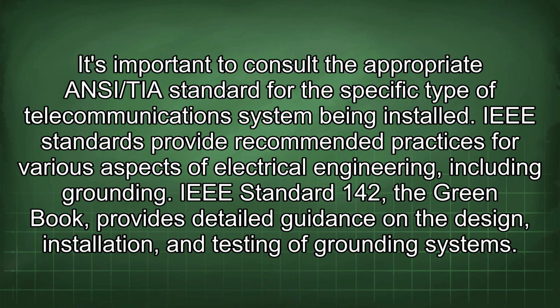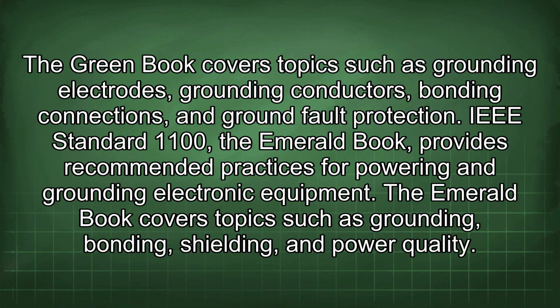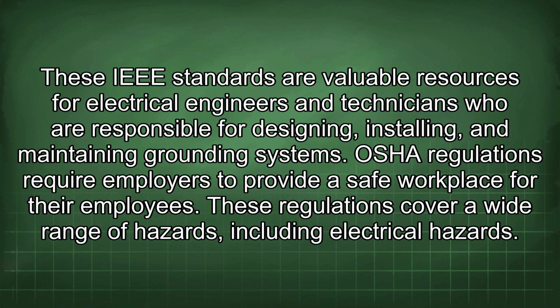IEEE standards provide recommended practices for various aspects of electrical engineering, including grounding. IEEE Standard 142, the Green Book, provides detailed guidance on the design, installation, and testing of grounding systems. The Green Book covers topics such as grounding electrodes, grounding conductors, bonding connections, and ground fault protection. IEEE Standard 1100, the Emerald Book, provides recommended practices for powering and grounding electronic equipment. The Emerald Book covers topics such as grounding, bonding, shielding, and power quality. These IEEE standards are valuable resources for electrical engineers and technicians who are responsible for designing, installing, and maintaining grounding systems.